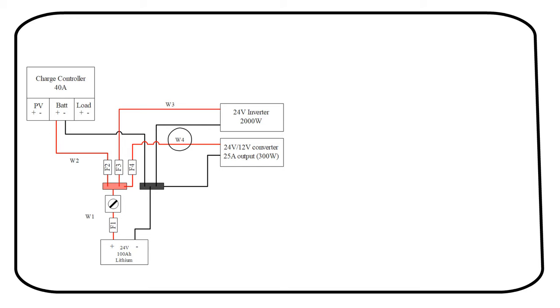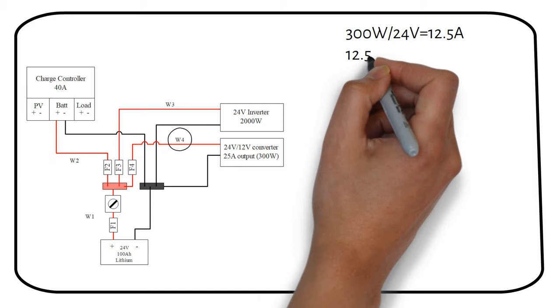For the last wire in our system, we divide the total power output of the DC to DC converter by the battery voltage. We become 12.5 amps. We then multiply by the safety factor to become 16 amps.